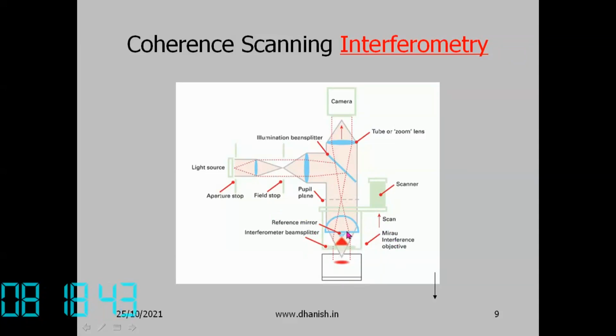You can identify the heights of various points over the entire surface at a time. So that's the advantage of this type of instrument. It's quite fast, so only the time to scan up and down. A certain distance it has to scan, and only when it is in focus can you measure the height. So how much the height difference is between different points is measured using that. Of course, we need a computer to do all those calculations. You can't manually see anything. So the entire surface is divided into a certain number of pixels, and in each pixel, the height is measured by this system. So this is for coherence scan interferometry. You have to scan slightly, but it's not scanning the entire surface, only a certain distance vertically, so that it's sort of focusing at various points to get the height at each point.